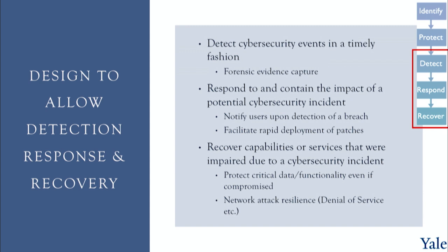So please realize that what this means is that you as a medical device manufacturer are responsible for monitoring your software after it goes to market, and we'll talk about that at the end. We'll talk about deployment. The deployment of patches means that the medical device manufacturer is going to provide those patches, which means that you have to have procedures in place to be notified of breaches, what the problem is, and to rapidly deploy patches to address issues like that. So you don't just sell a product and forget about it. You have to stand behind it throughout its life cycle.